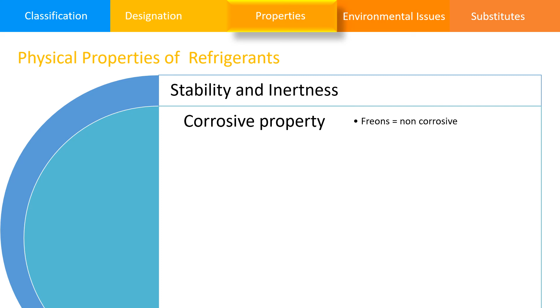It must be taken into consideration while selecting the refrigerants. The freons are non-corrosive with practically all metals. Ammonia can only be used with steel and water. Sulfur dioxide is non-corrosive, but when it is mixed with water, it will form sulfuric acid, which is highly corrosive.